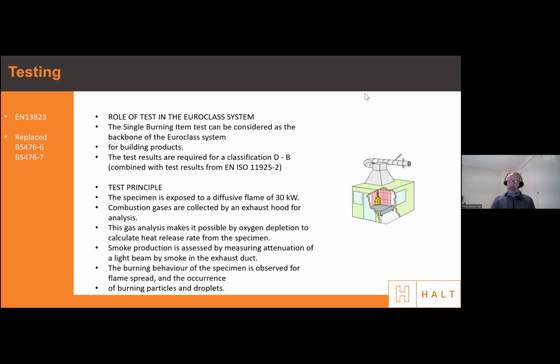The SBI test is very comprehensive. It's the product or material that you're testing. It's a requirement that you go through this process and it's exposed to a 30 kilowatt flame. During the testing process, combustion gases are measured, smoke production is measured, heat release rate is measured, fire intensity growth rate is measured, and if you think about it as a total system, we're testing a material to be used in construction, and we should be testing that material in construction and as close as possible to its field of application.